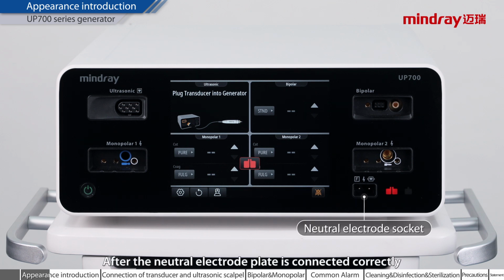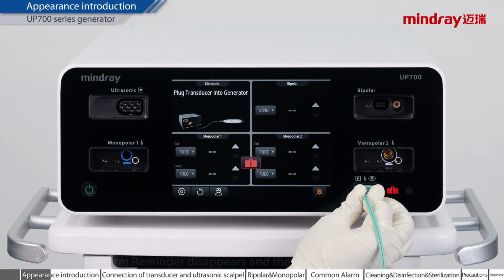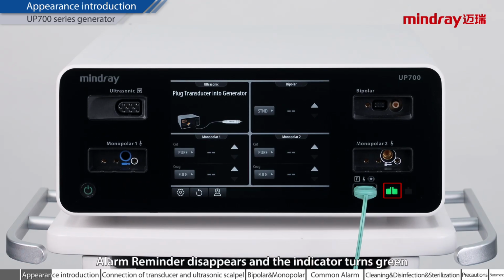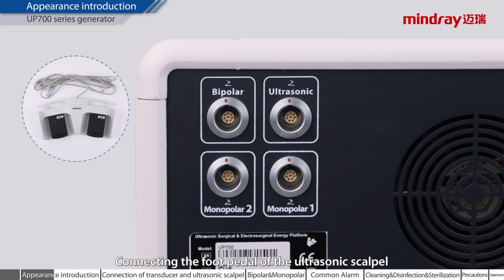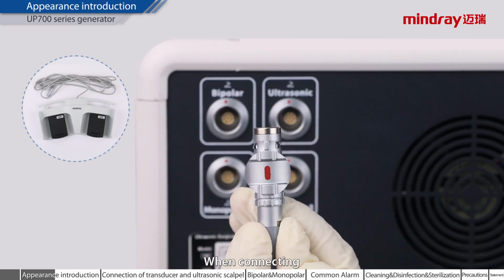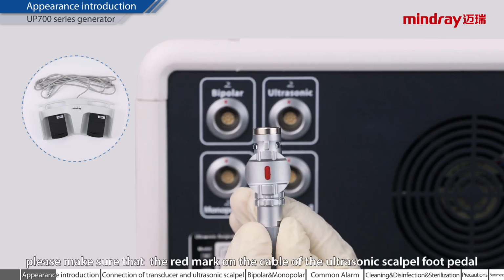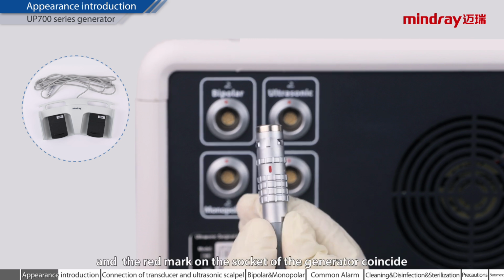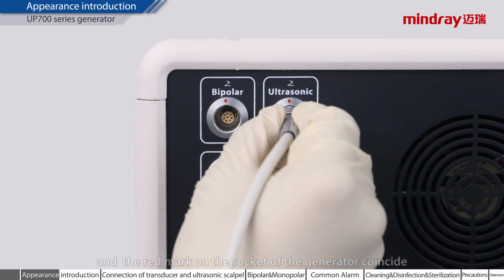After the neutral electrode plate is connected correctly, the alarm reminder disappears and the indicator turns green. Connecting the foot pedal of the ultrasonic scalpel. When connecting, please make sure that the red mark on the cable of the ultrasonic scalpel foot pedal and the red mark on the socket of the generator coincide.